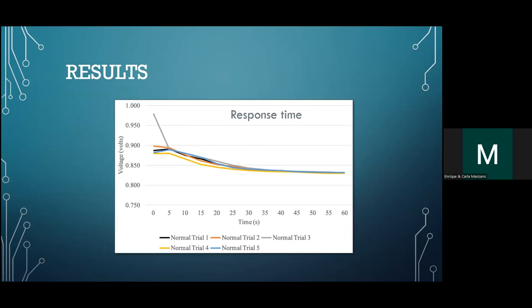If you look at our response time, the response for every measurement starts at some value — high or low depending on conditions — then stabilizes. You will get a stabilized output after about 40 seconds. This was clearly observed across the low, normal, and high solutions. After 40 seconds we can get a reading, and besides signal conditioning procedures, we take as many measurements as possible to minimize error using a simple average.